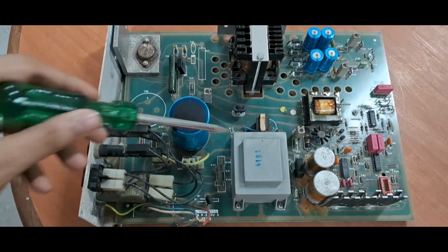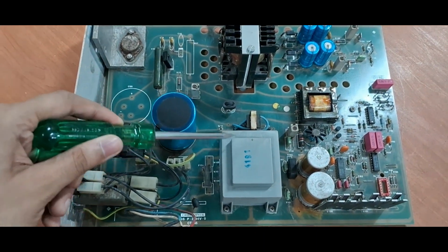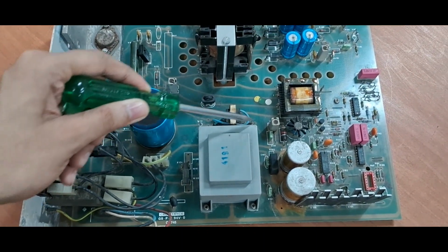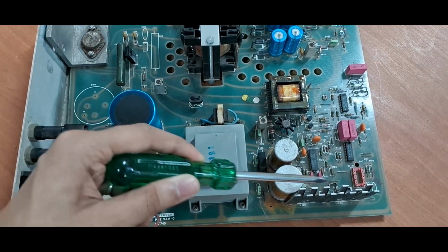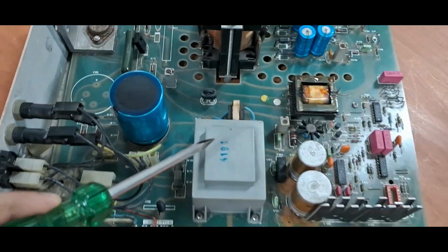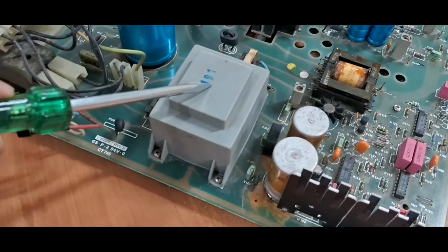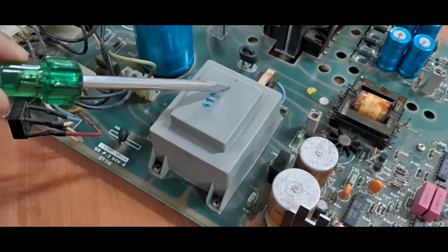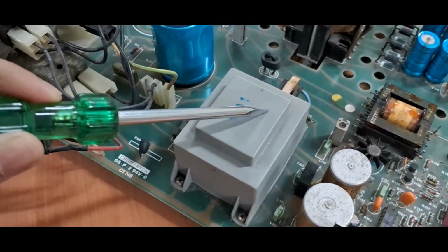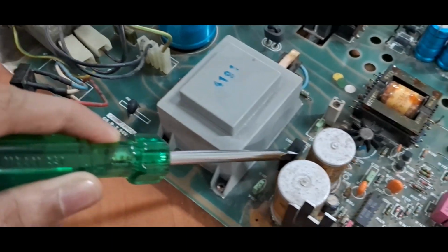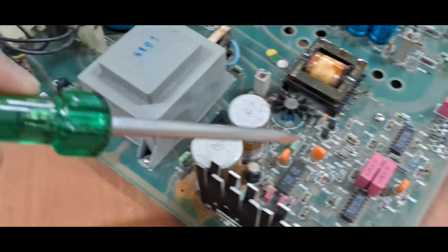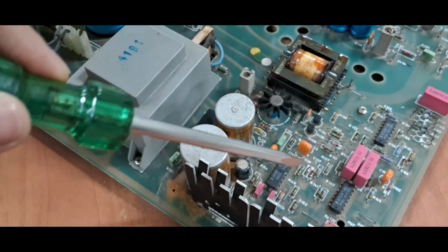So this unit has one mains transformer, which is the low frequency transformer. This is used to generate the auxiliary power supply for all of the control circuit. It's one of those seal type transformers, potted. You can still buy these, it's a very common package. After that we have a bridge rectifier, and then we have two capacitors which supply the control circuitry.